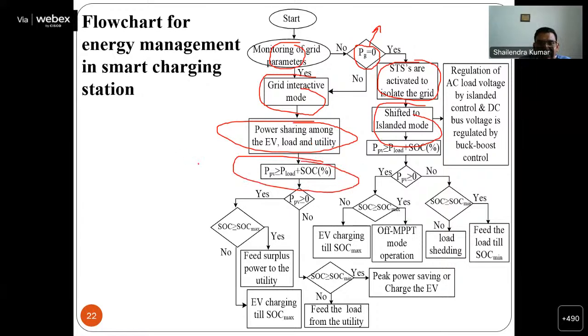After that we have to apply one condition: is PV power more than the loads, and what is the SOC of the battery? If yes, we check the SOC limit of the battery at the charging station. If it is fully charged and the SOC is hitting the higher limit, then we can feed extra power to the grid. If not, we can charge the battery till SOC max. On the other side, if no, we check the SOC again, and if the SOC is above the limit, we can discharge the battery at the charging station and charge the vehicles. If no, we can feed the load from the utility grid. The onboard charger and all these things will be shifted to the grid.